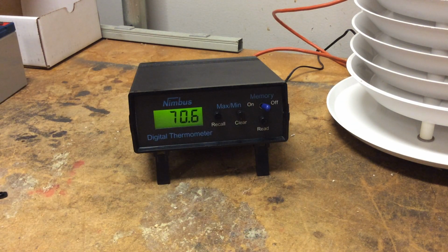Some other troubleshooting things: if your readings don't change, the instrument is left in the memory mode. Again, another one of those. Readings are always minus 99.9: the probe is disconnected or there is an open short somewhere. So you want to check to make sure the probe is plugged in and the cable has not been damaged. Another one is that the readings are always 255.5. Temperature is much too high, or there's a short in the probe or cable.